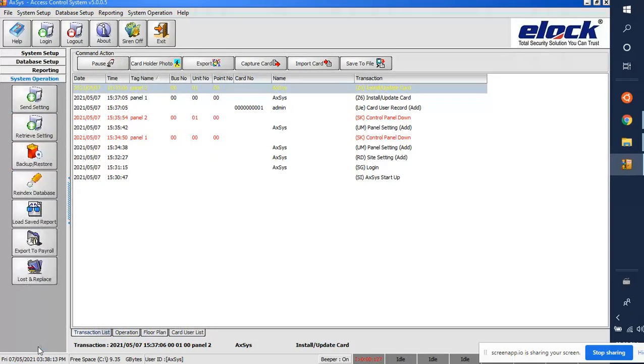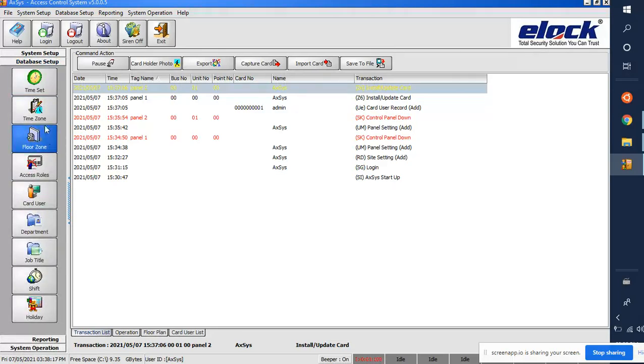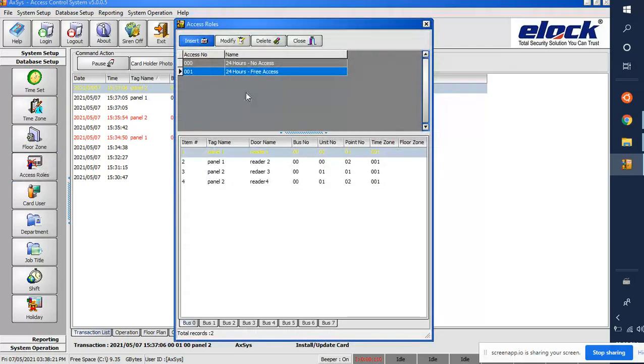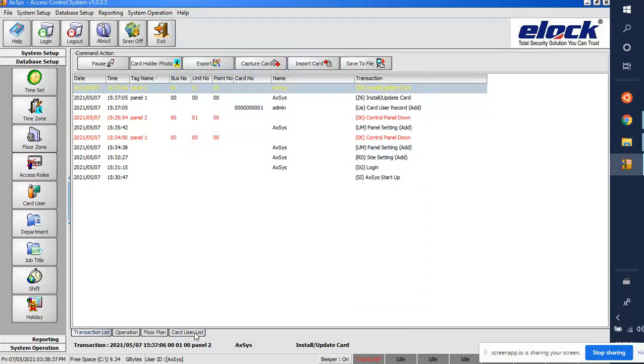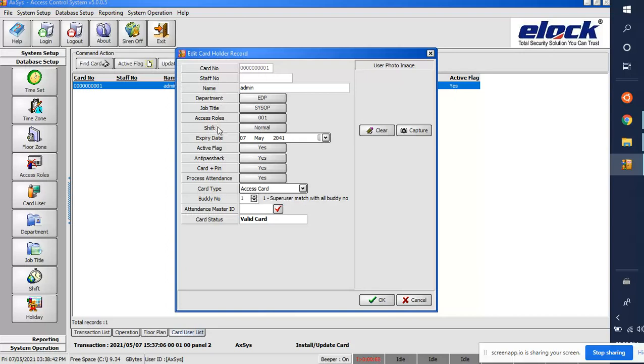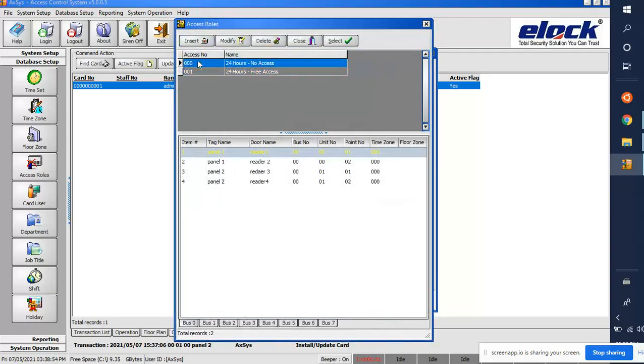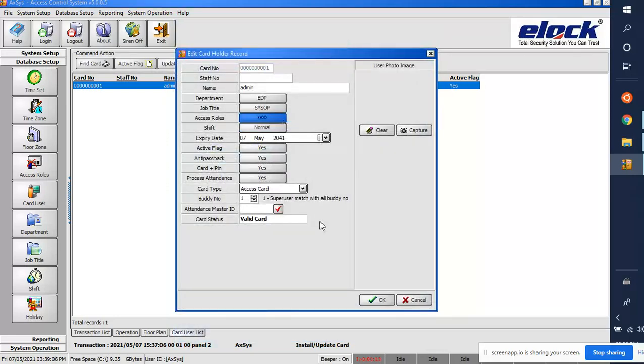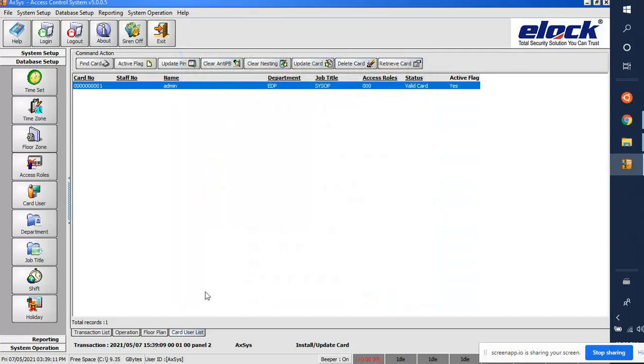To control this, we need to create an access role. Go to System Operation > Database Setup > Access Roles. Access number 000 means no access (24 hours). Access number 001 means 24-hour full access to all doors. If a user's access role is 001, they can access all readers. If it's 000, they have no entry at all.